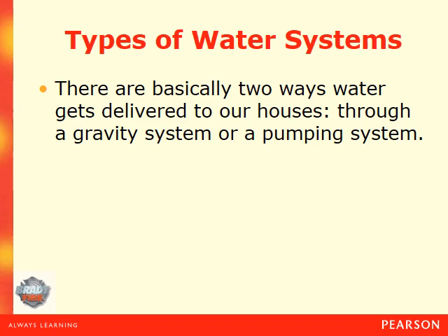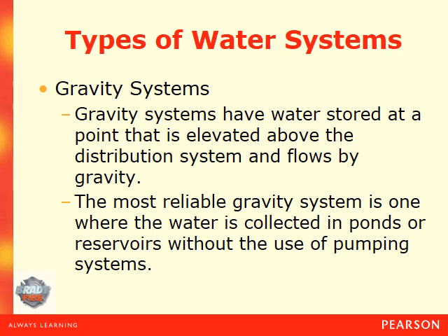There are two basic ways water gets delivered to our homes and hydrants: one is through a gravity system, the other is through a pumping system. Gravity systems have water stored at a point elevated above the distribution system and flows by gravity — a good example being a reservoir high up on a hill or mountain, with feeder lines going into the community. Other examples are the water tanks you see throughout your community. The most reliable gravity system is one where water is collected in ponds or reservoirs without the use of a pumping system.